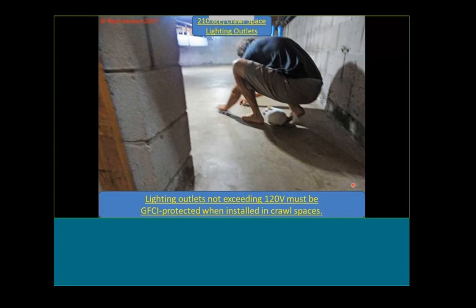Another change we made is a safety requirement for crawl spaces. And man, I'll tell you, I am so glad they put this into the code. Lighting outlets in crawl spaces must be GFCI protected up to 120 volts.